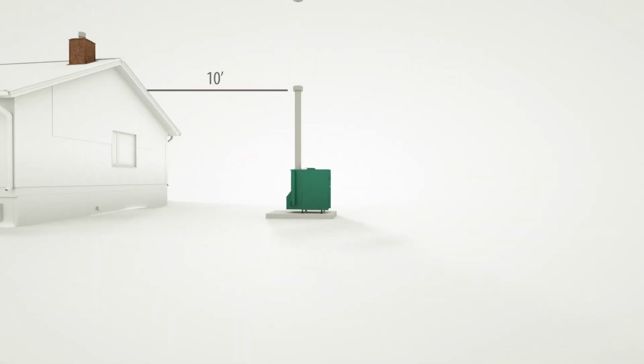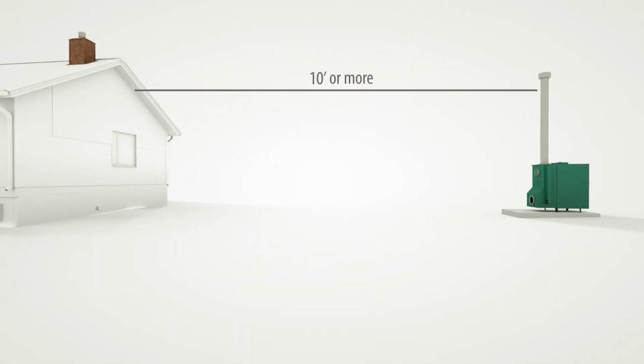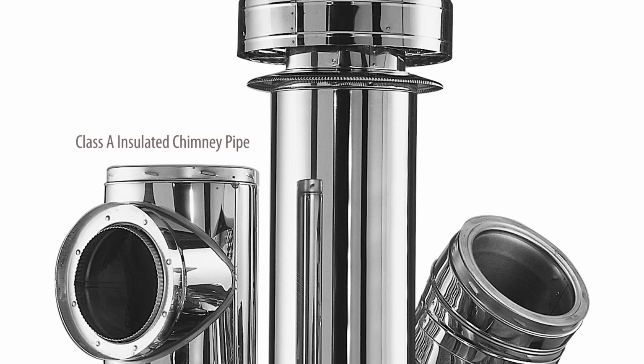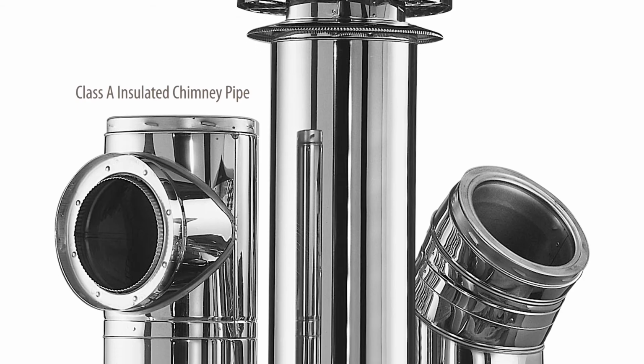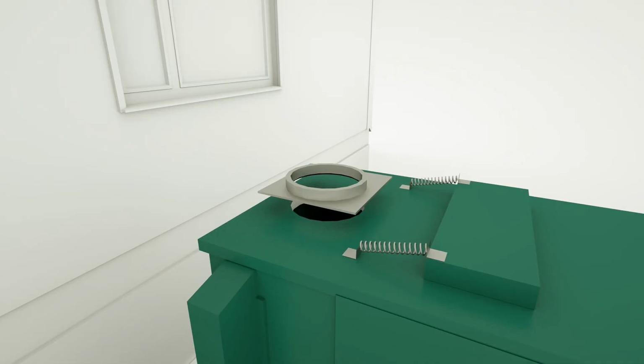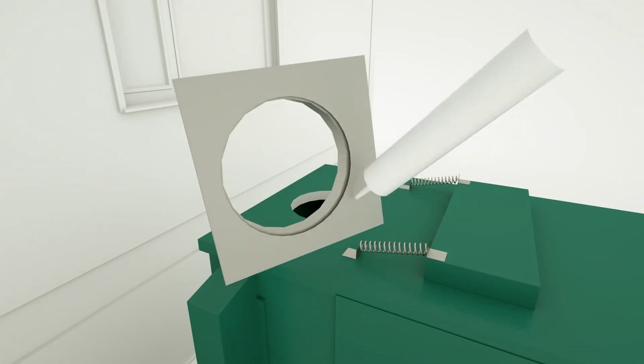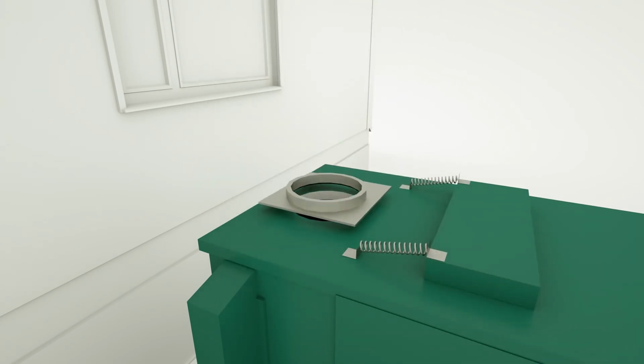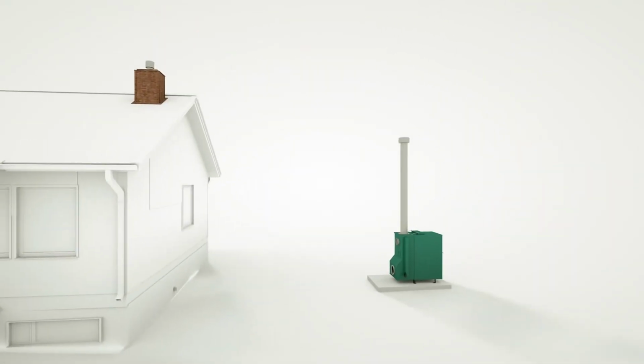If your furnace is located 10 feet or more away from your home, a minimum of 6 feet of Class A insulated chimney pipe is required. The installed anchor plate accepts ShelterPro chimney pipe. If you desire to use another brand, you will need to change the anchor plate to one designed specifically for that product. It is critical to properly seal the anchor plate and chimney pipe to the unit.